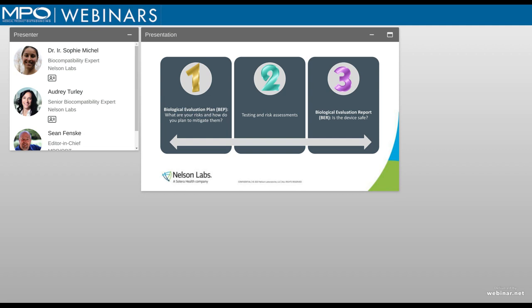So I would like to remind everyone that, of course, irritation is an endpoint of evaluation for medical devices, but it's actually only one of the endpoints. There can be several different endpoints depending on the classification of your product. But what is important is to see that ISO 10993-23 actually asks you to evaluate for irritation as part of a risk assessment process, which is exactly going hand in hand with what is requested in ISO 10993-1, which also asks you to evaluate the safety of your final product as part of a risk assessment.